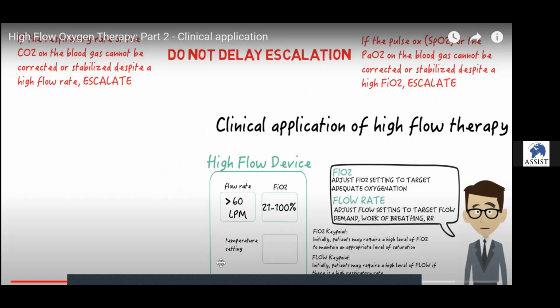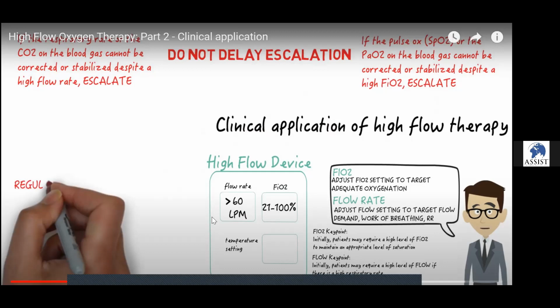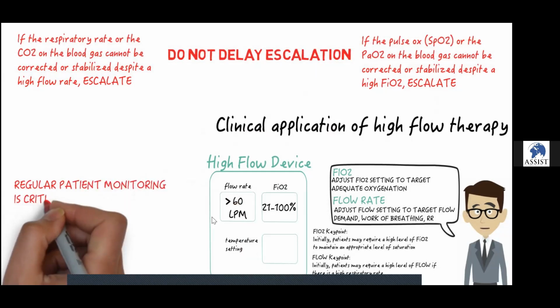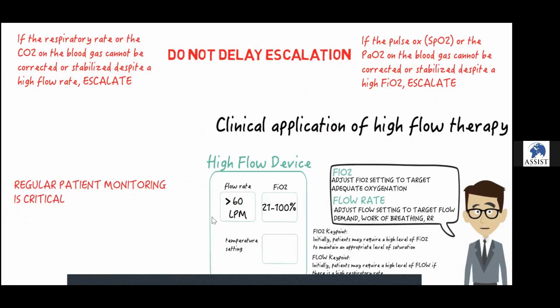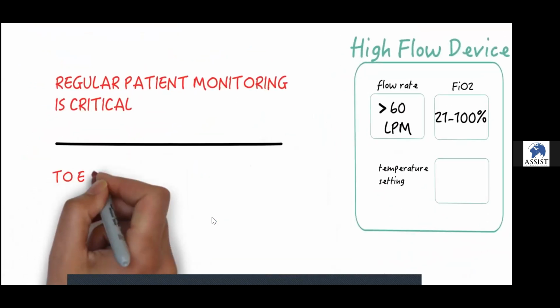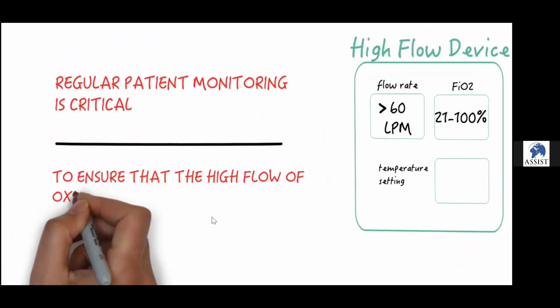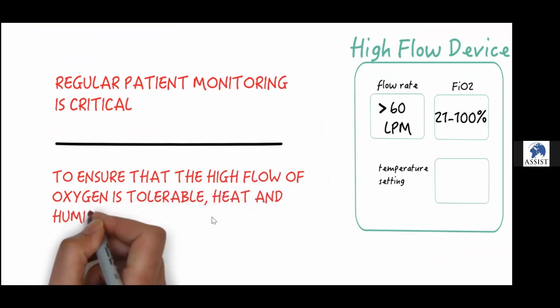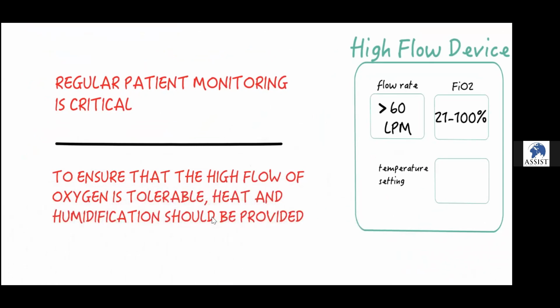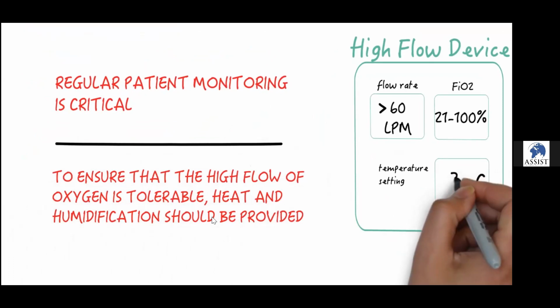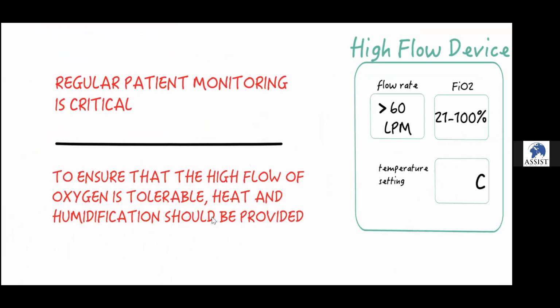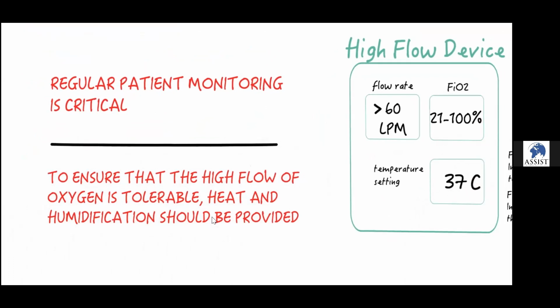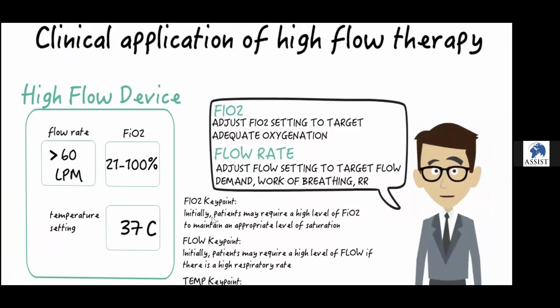Okay, now remember, because there are no patient alarms and data monitoring is not available on high-flow oxygen devices, regular patient monitoring is critical. There is one more control in high-flow therapy, and that's the temperature setting. To ensure that the high flow of oxygen is tolerable, heat and humidification should be provided. The exact appropriate temperature setting is debatable, and there currently exists no temperature standard. Some suggest to start at 37 degrees Celsius, others suggest start lower. But the key point in temperature setting is to adjust the temperature based on patient comfort and tolerance.